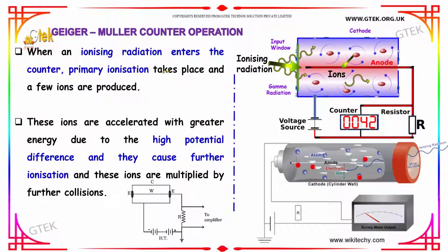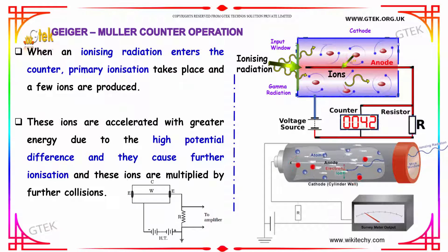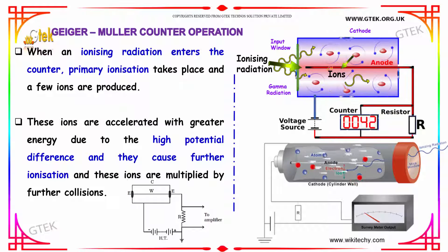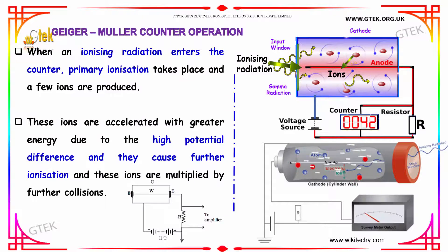When an ionizing radiation enters the counter, primary ionization takes place and a few ions are produced. These ions are accelerated with very high energy due to the high potential difference and they cause further ionization, and these ions are multiplied by further collision.